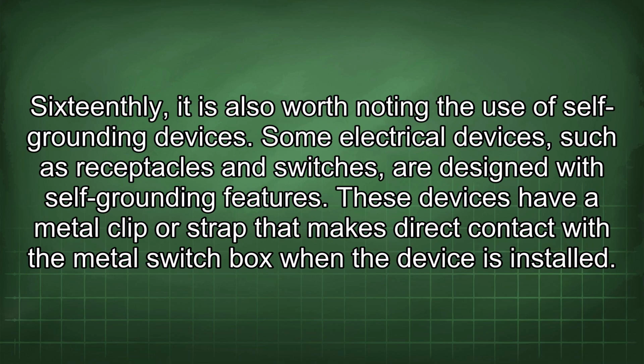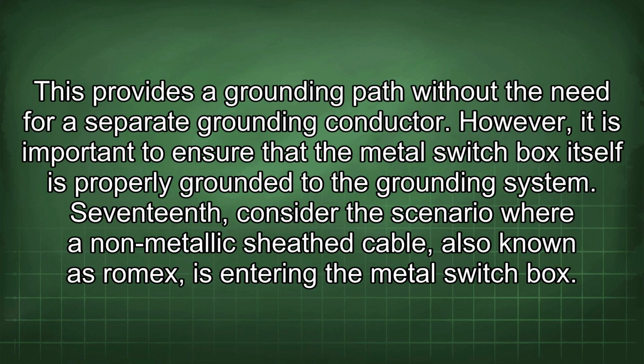16thly, it is also worth noting the use of self-grounding devices. Some electrical devices, such as receptacles and switches, are designed with self-grounding features. These devices have a metal clip or strap that makes direct contact with the metal switch box when the device is installed. This provides a grounding path without the need for a separate grounding conductor. However, it is important to ensure that the metal switch box itself is properly grounded to the grounding system.